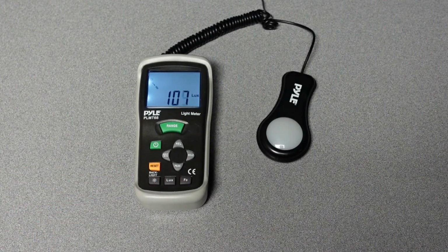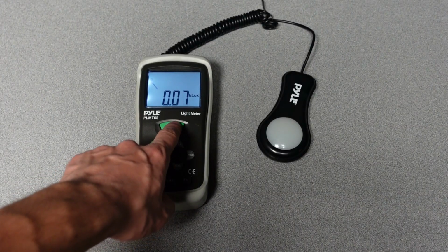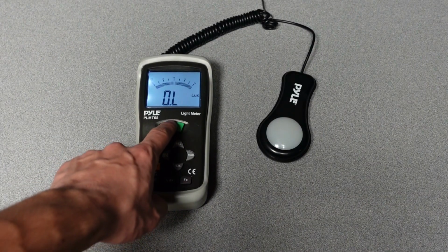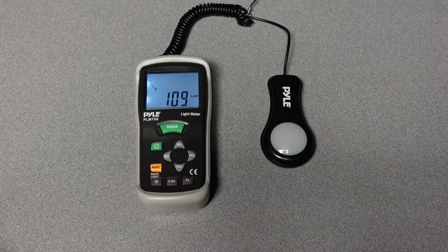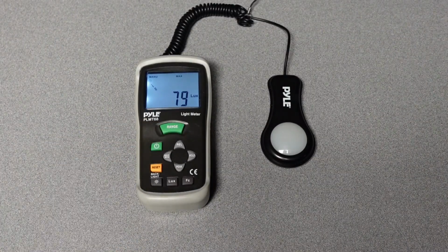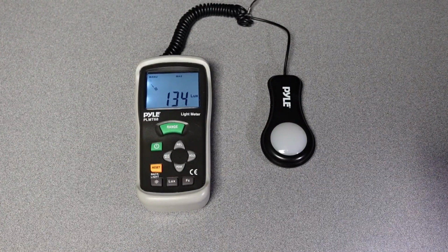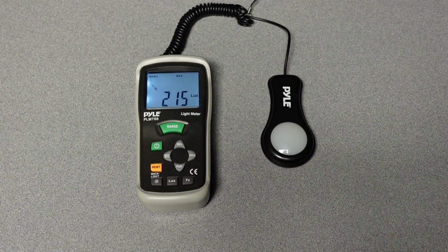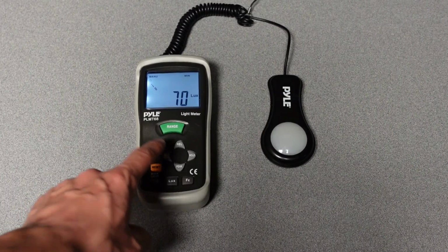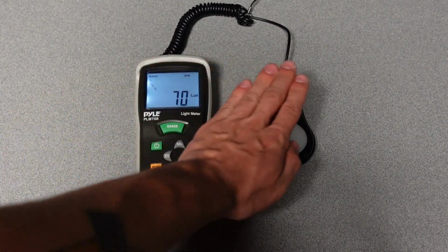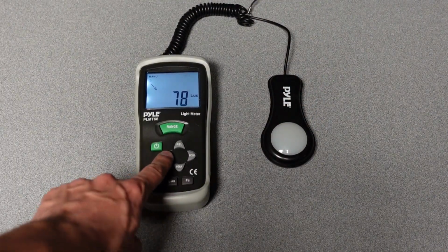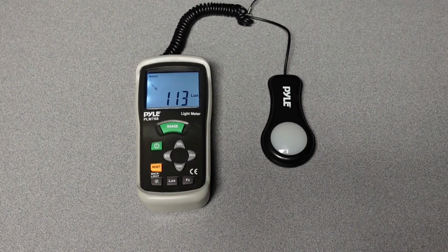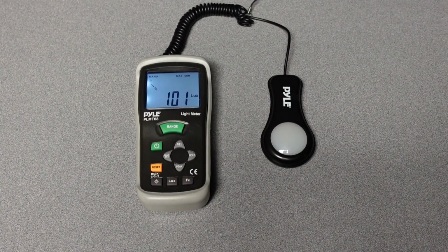The range of the light meter can also be changed to account for the environment in which it will be used. These ranges can be found in the manual. The light meter is equipped with a max/min button. The first time this button is pressed, the meter begins recording and displays only the maximum. The second time it is pressed, it will display only the minimum, but continues recording. The third time it is pressed, it will display all values and continue recording. Holding the max/min button will stop the recording.